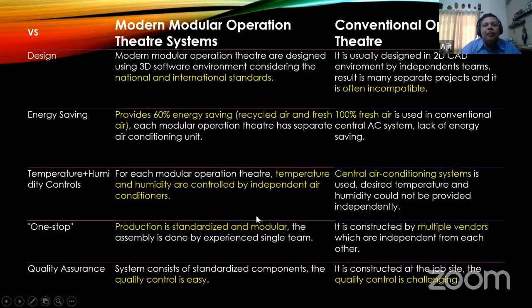We have two different types of operation theatre systems: the conventional operation theatre and the modern modular operation theatre system. The basic difference is that a modular system is required when there are multiple operation theatres, and each OT is a unit by itself with independent humidity and temperature controls, whereas in a conventional operation theatre suite, all controls are centrally located, so you cannot change the humidity or temperature in each individual theatre.